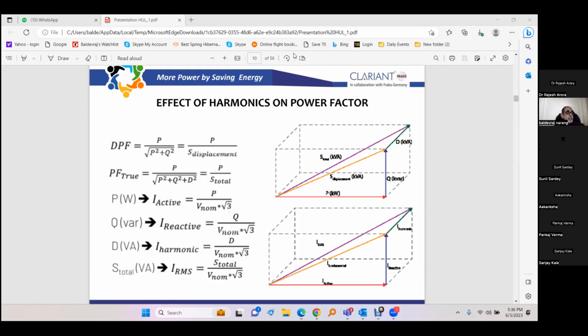Even if we make the requirement mandatory, even if people start putting in STATCOMs, the situation we have been facing, the isolations that have been happening, will continue to happen. In the steady state condition, whether it is a switched capacitor bank, a shunt reactor, or a STATCOM, both work equally well. So there is no problem in that.